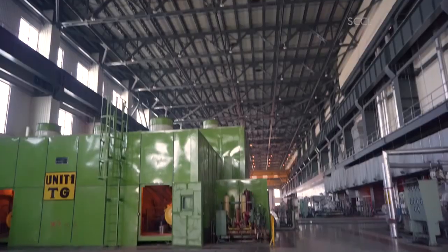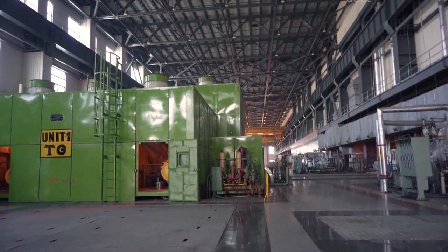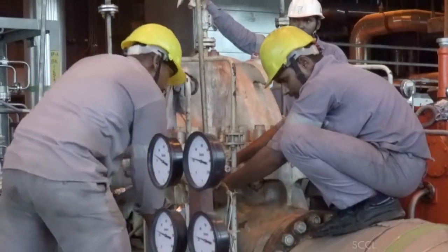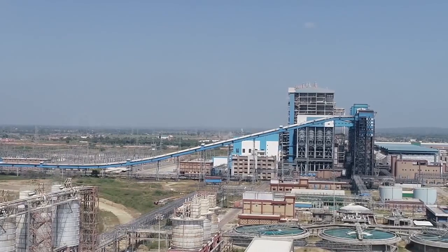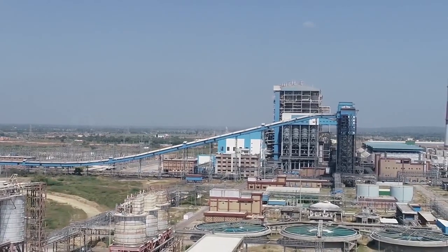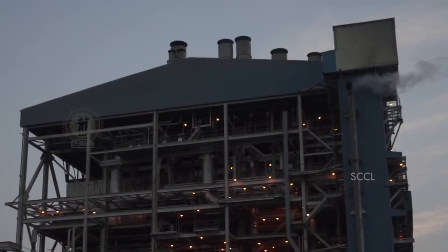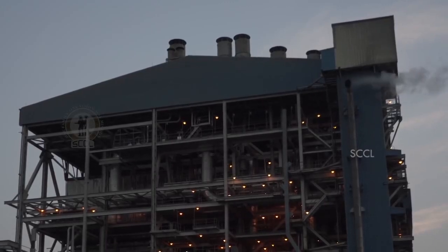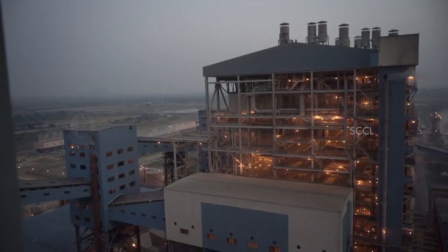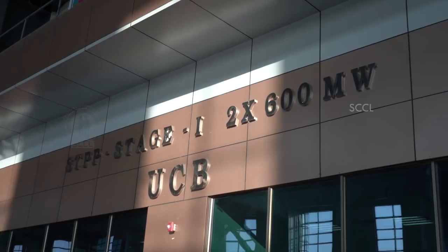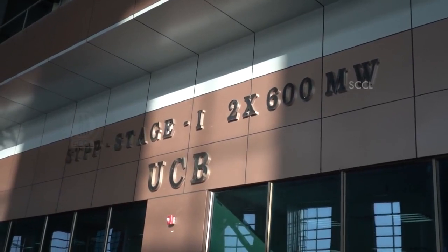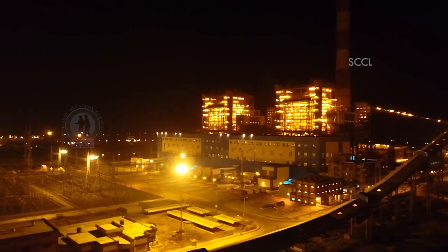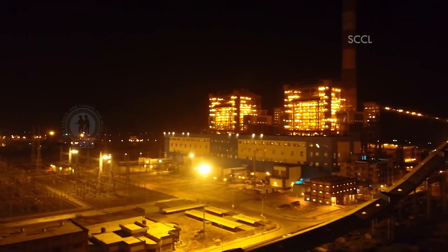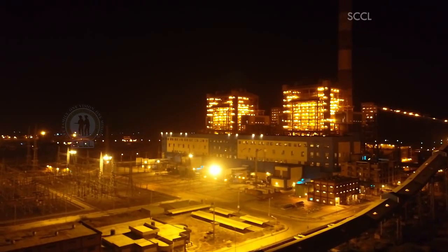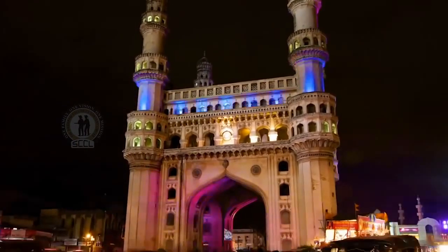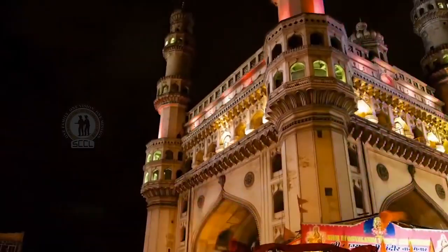These thermal power units achieved 100% PLF, plant load factor, many times, and the power plant has achieved 5th position amongst all the thermal power plants in the country in 2017. Now, let's see how electricity is generated from coal by taking a tour of STPP, a coal-fired power plant. This plant has 2 generating units, each of 600 megawatts, that produce 1200 megawatts of electricity at full capacity. This one power plant can produce enough electricity to supply to the needs of twin cities Hyderabad and Secunderabad in Telangana state.